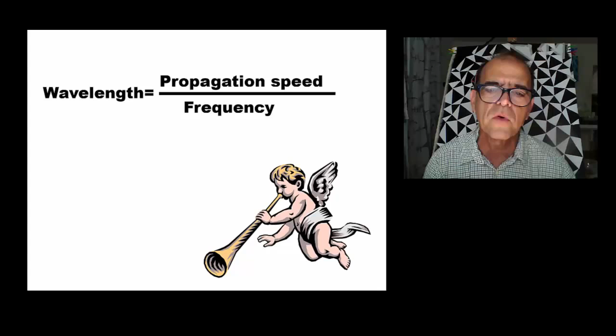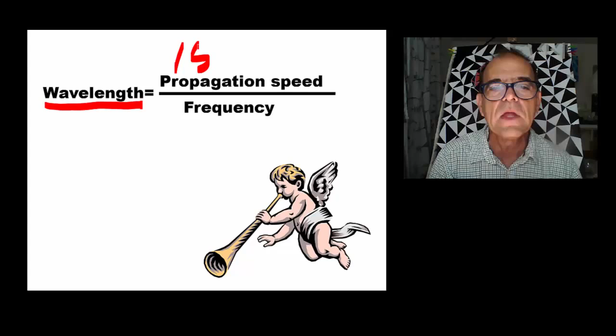You have here the formula of the wavelength. This is a very important formula. This is something that you must remember, that you must understand very, very well. Wavelength, that is the item that we are studying, is equal to propagation speed, 1540 meters per second, over the frequency of the transducer that you are using: 3 megahertz, 5 megahertz, 7.5 megahertz, depending on what organ you are scanning.